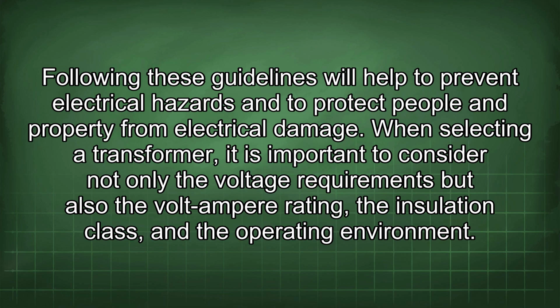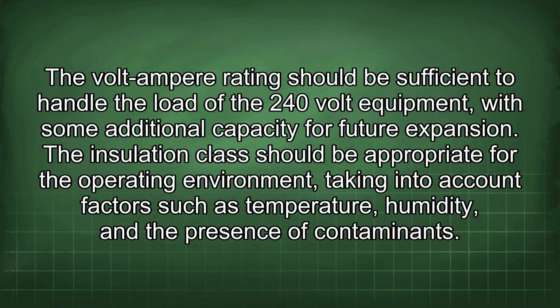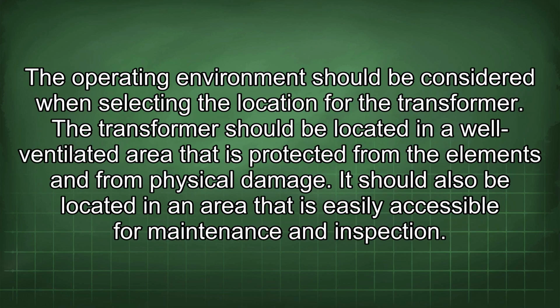When selecting a transformer, it is important to consider not only the voltage requirements but also the volt-ampere rating, the insulation class, and the operating environment. The volt-ampere rating should be sufficient to handle the load of the 240-volt equipment, with some additional capacity for future expansion. The insulation class should be appropriate for the operating environment, taking into account factors such as temperature, humidity, and the presence of contaminants. The operating environment should be considered when selecting the location for the transformer.